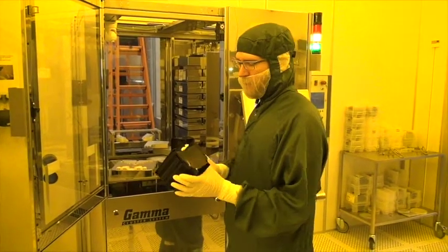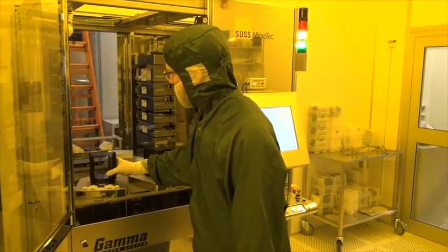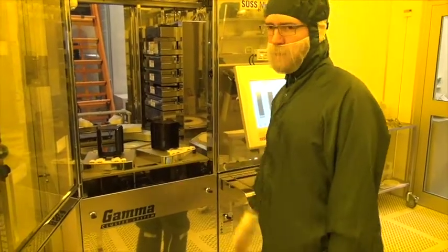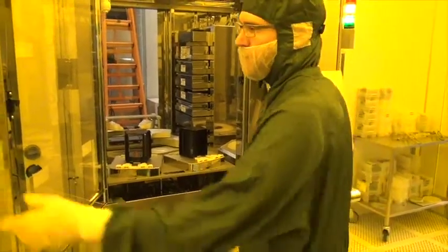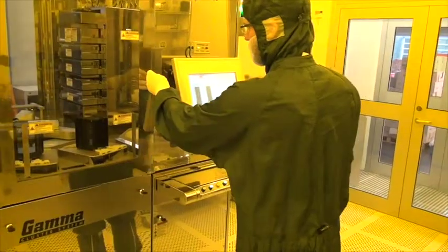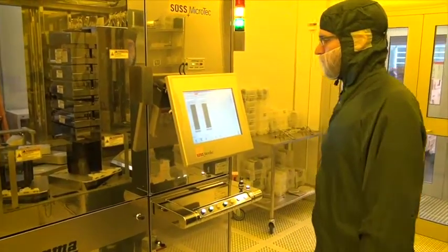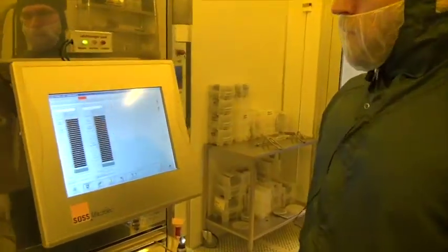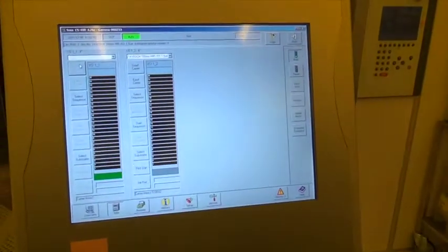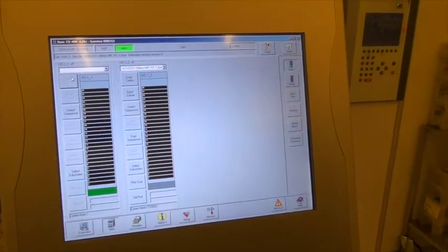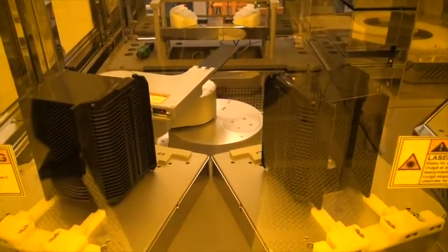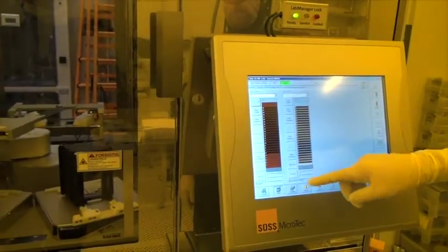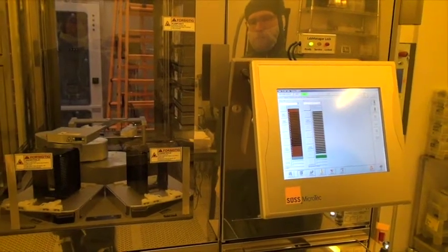Now I'm loading my wafers for processing. Notice that the input output stations are not designated for input and output, you can just choose whichever you want. Again close the door, press the door interlock and press load carrier to load the cassette, verify that the position is correct and press load carrier on the output cassette.